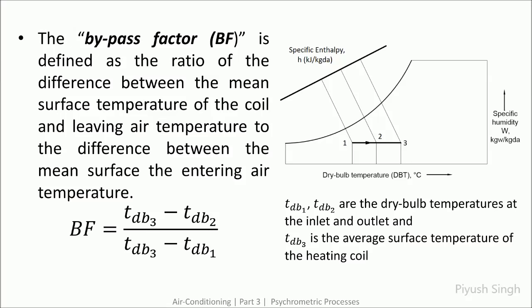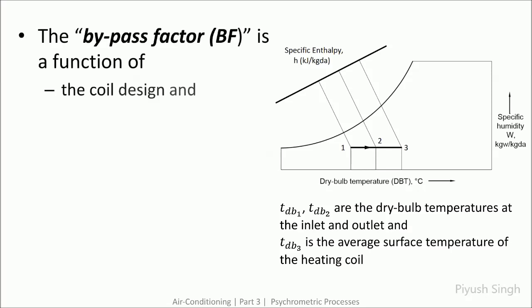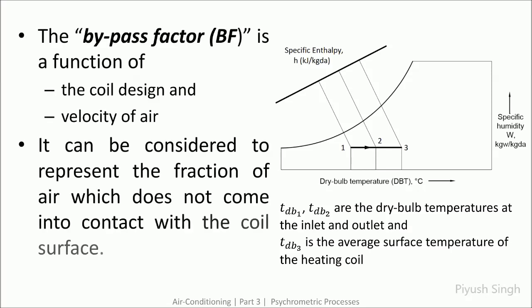In case of the coil, the total desired change in temperature was the difference between TdB3 and TdB1 — that is the denominator. What could not be achieved was TdB3 minus TdB2. So this ratio gives us the bypass factor. The bypass factor is a function of coil design: higher the number of coils, smaller is the bypass factor; and higher the velocity of air, higher is the bypass factor.